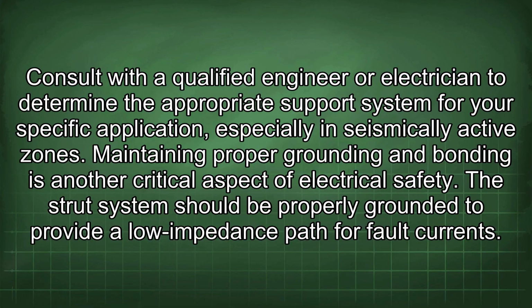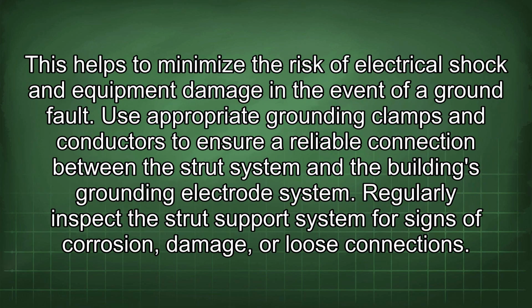Maintaining proper grounding and bonding is another critical aspect of electrical safety. The strut system should be properly grounded to provide a low impedance path for fault currents. This helps to minimize the risk of electrical shock and equipment damage in the event of a ground fault. Use appropriate grounding clamps and conductors to ensure a reliable connection between the strut system and the building's grounding electrode system.